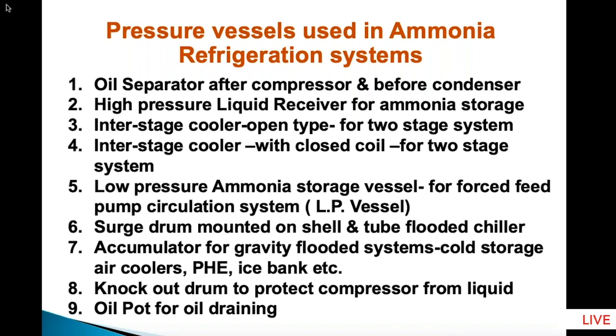The main vessel which is used is an oil separator after the compressor and before the condenser. This is an important item because it separates out the oil and does not allow oil to go into the system. The second important vessel in the refrigeration plant is the high pressure liquid ammonia receiver. This ammonia receiver is for accumulating the entire charge of refrigerant in the system. The third item is the interstage cooler, which is of different types. One is the open type interstage cooler and one is the closed type interstage cooler. So these two coolers are important depending upon the system design.